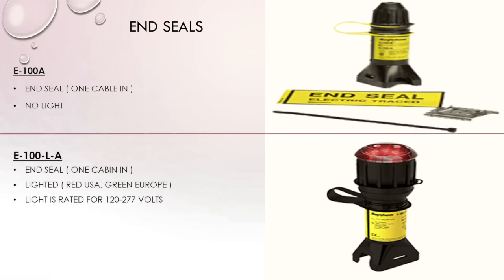At the end of every heat trace cable run you need an end seal. We have two types: the E100A, which is one cable in with no light, and the E100LA, which is a lighted end seal — also one cable in. In the US the light is red; in European locations it's green. The US lighted version operates from 120 volts up to 277 volts, covering 120V, 208V, 240V, and 277V. Those are our Class 1 Div 2 industrial components.